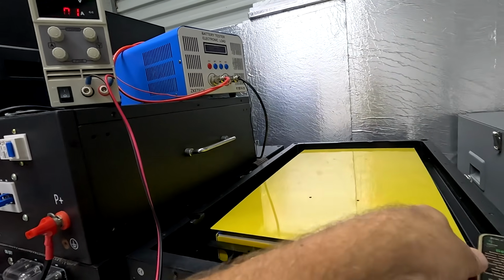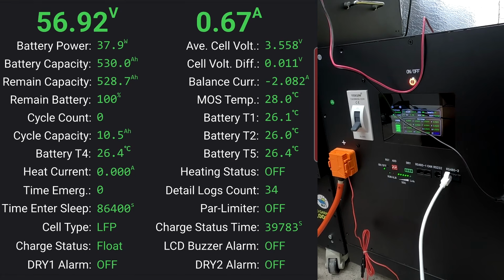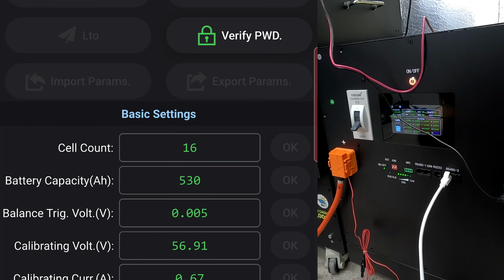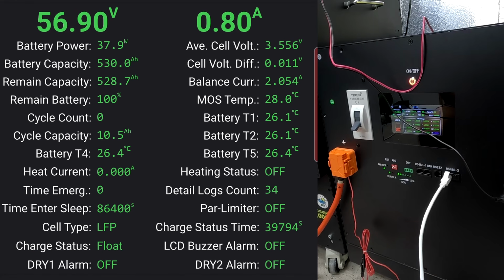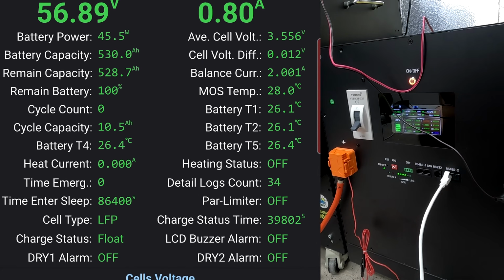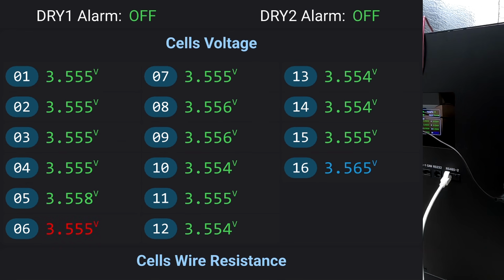57 volts we have reached now. So there we go, you can see it, 56.9 volts. We've got a deviation of 11 millivolt. Balancer is still running, I have set the balance trigger voltage to 5 millivolts, so why not let it balance to 5 millivolt. It's still taking 0.8 amps or so, but all the cells here you can see are around 3.555 volts. Cell number 16 is the highest at the moment, slightly higher, 10 millivolt higher, but the balancer is still running, and we give it another 2 minutes or so and then we start the test. I think under 10 millivolt deviation now, that is fairly top balanced, right?